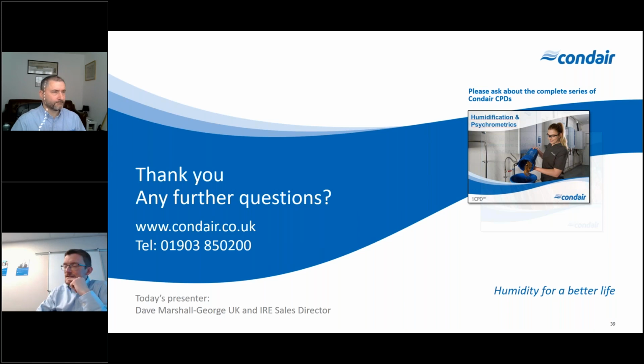Yeah, perfect. And one last question for you, Dave, if that's okay. This one is from a gentleman called Stephen, and he asks, when you are looking at a desiccant dryer fitted with a heat recovery option, does the regeneration fan have to be of a high temperature function? So in other words, does it have to be a specific fan with a rating up to potentially 50 or 70 degrees instead of the standard?